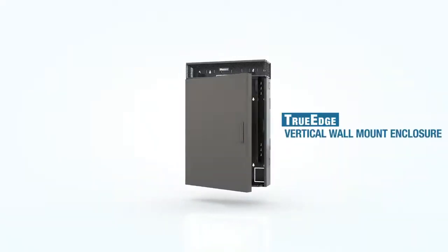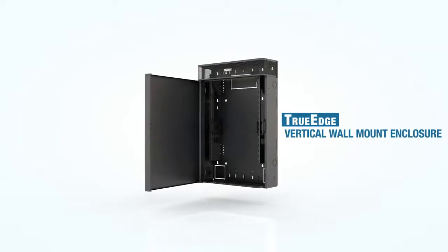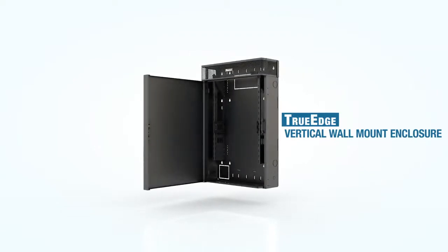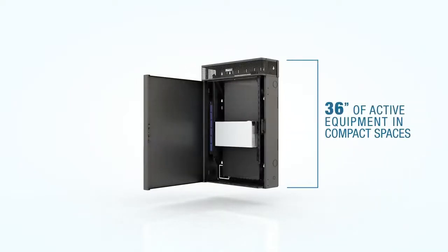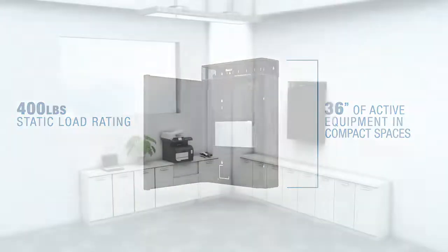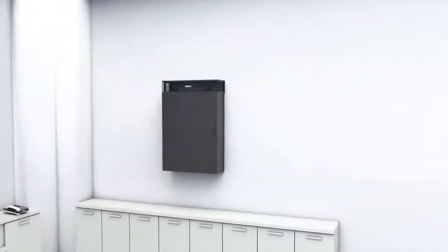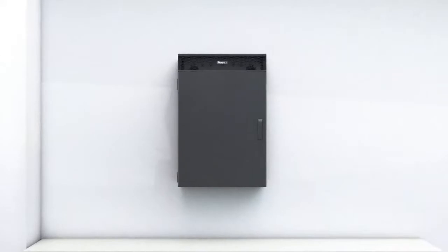Panduit's TrueEdge vertical wall mount enclosure is a space-efficient way to deploy switch and server systems in an open architecture environment. It vertically mounts up to 36 inches of active equipment in compact spaces with a static load rating of 400 pounds.